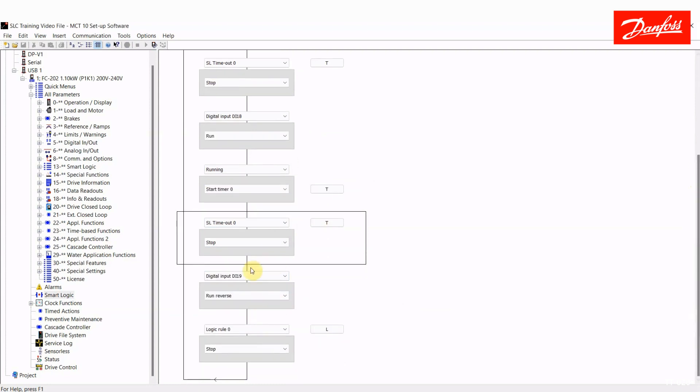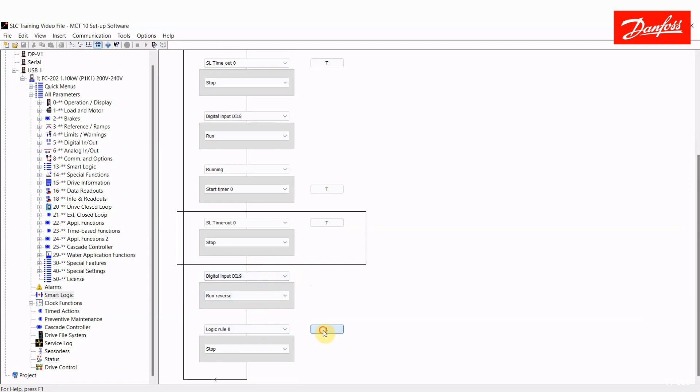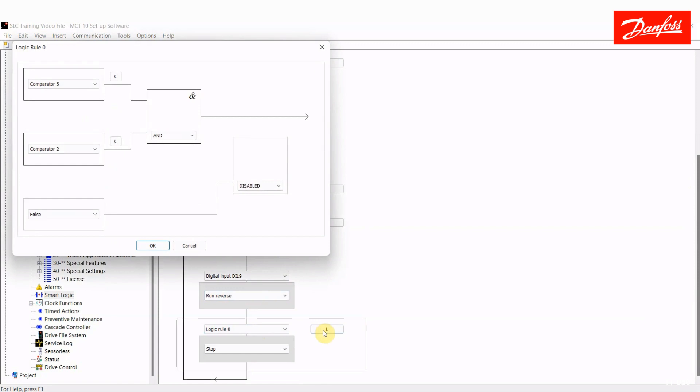Now, if someone were to press that same button again, digital input 18, nothing would happen. It's waiting for someone to close digital input 19. That would be your close button. When digital input 19 is pressed, the drive is going to run in reverse. Then, I'm going to come down and wait for my next event to become true, which is logic rule 0. So, when 19 is pressed and the drive is running in reverse now, I will continue to do that until logic rule 0 is true. Logic rule 0 is defined as comparator 5 and comparator 2.